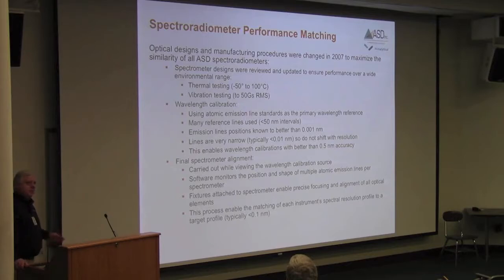So this allowed us to do our calibrations using emission lines, which, from the standpoint of our spectrometers, are infinitely narrow lines, because they're well under any kind of resolution that we're in, more in the 5 to 10 nanometer range. So it really improved the accuracy of the wavelength scale calibration. And then we built a lot of jigs and fixtures that we use, so we could watch those lines and tune the spectrometer to match the resolution profile that we're targeting. And all this means that if you get two FieldSpec standard resolution images together, they're going to match each other quite closely.